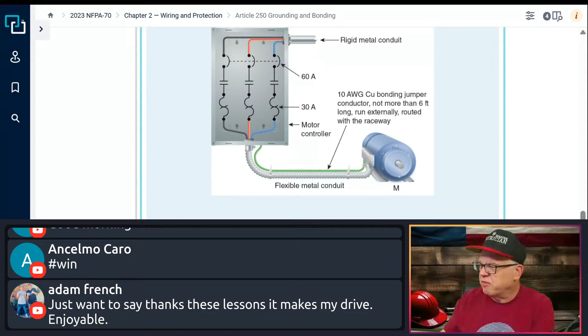So this would be acceptable, but you are limited in length, okay? That type of scenario. All right, let's see. Let me close that down. Now, there is obviously exceptions, and this one here says an equipment bonding jumper or supply side bonding jumper longer than 6 feet, okay, so you're limited to the 6 feet, longer than 6 feet shall be permitted at outside pole locations for the purpose of bonding or grounding isolated sections of metal raceways or elbows installed in exposed risers of metal conduits or other metal raceways.